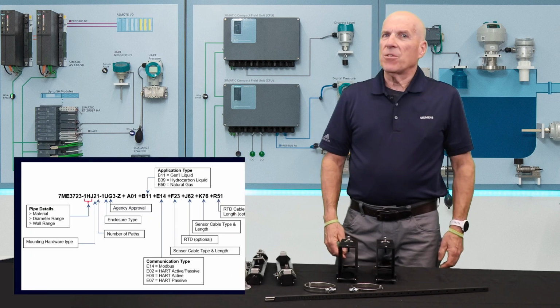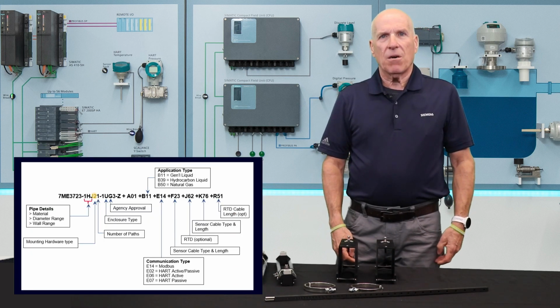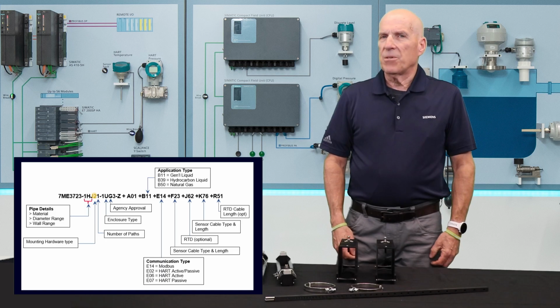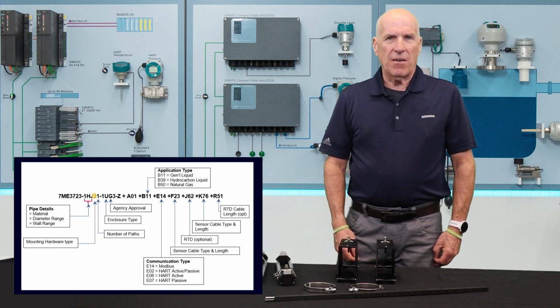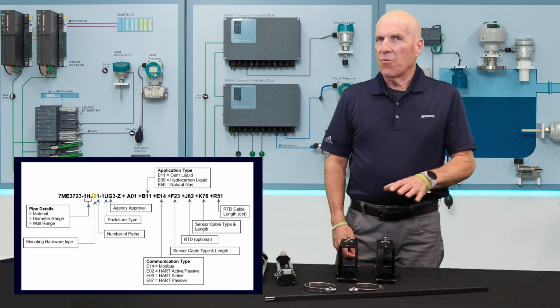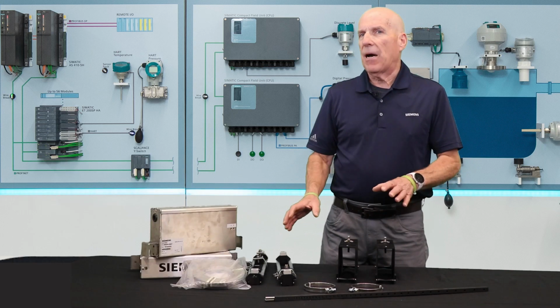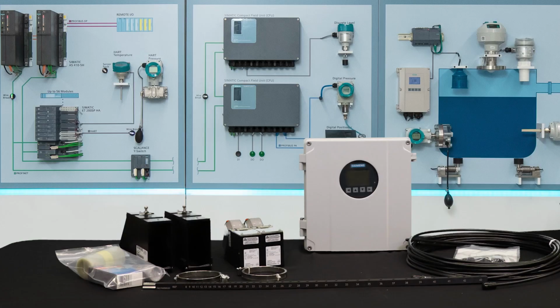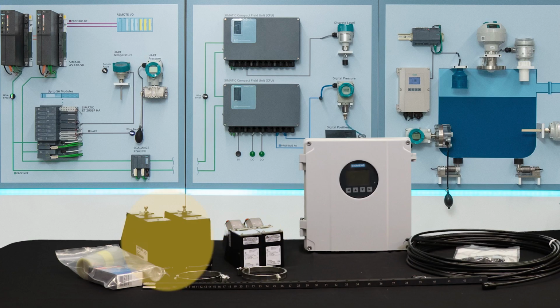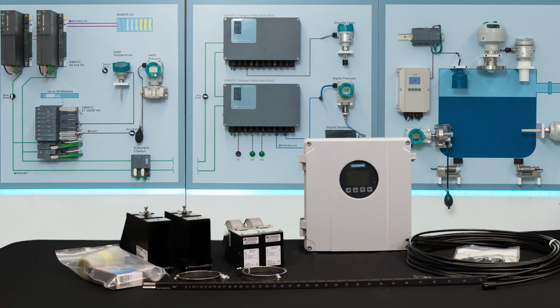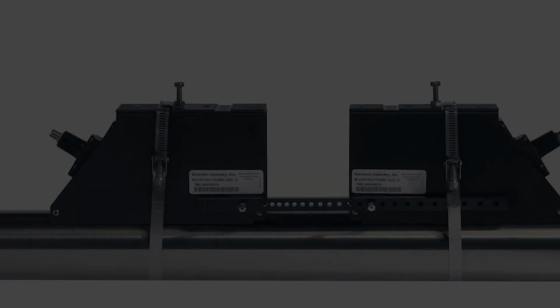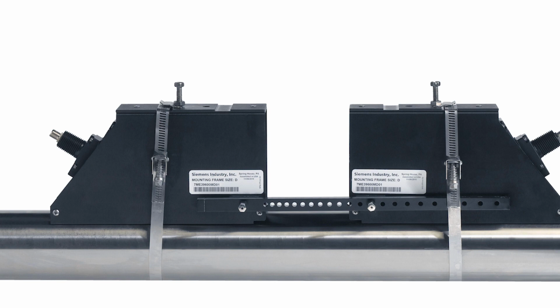The type of mounting hardware supplied is identified by the numerical code of your system part number in position 11. The standard identifier is 2 and designates either frames or tracks depending upon the pipe size. As I mentioned, my system came with size D1H high precision sensors, so I received mounting frames and a spacer bar. If you receive any size C, D, or E sensors, you'll typically receive mounting frames as well. The frames are strapped to the pipe with the stainless steel straps at the appropriate spacing that is set using the spacer bar.